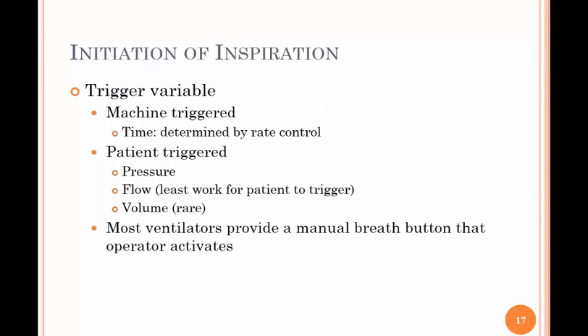If it's patient triggered, it can be set at pressure or flow, and even volume, though that is rare. Most ventilators provide a manual breath button that the operator activates — however many times you push the button, that's how many breaths the patient gets. The three trigger variables are time, pressure, and flow.